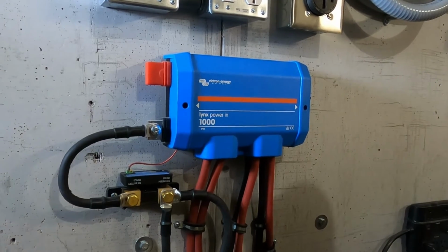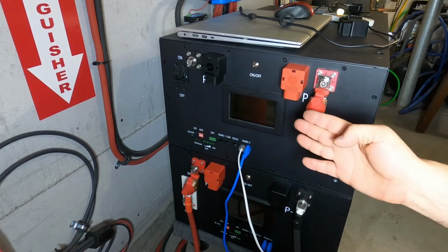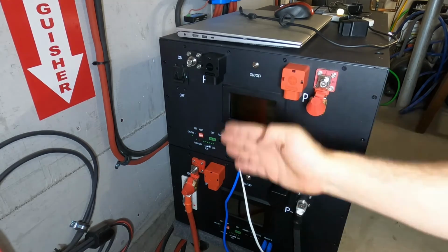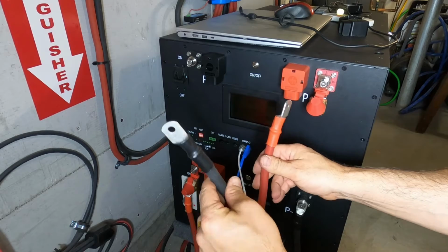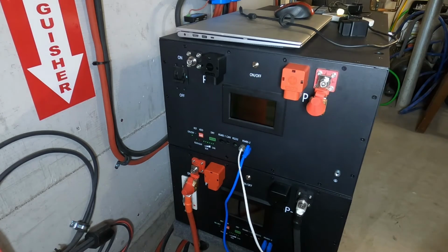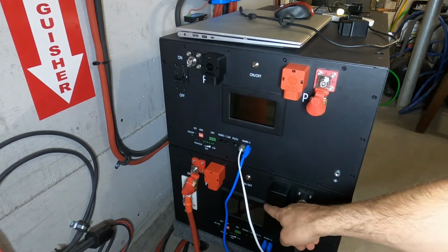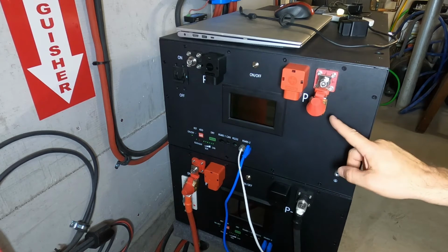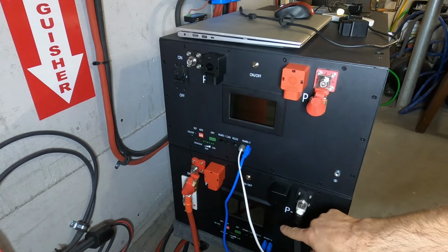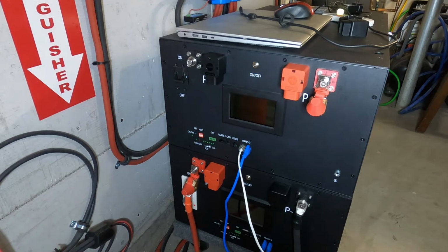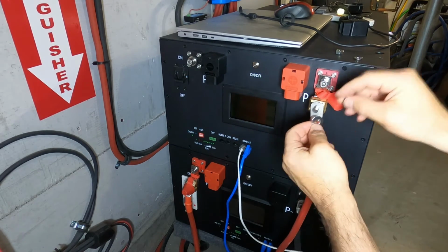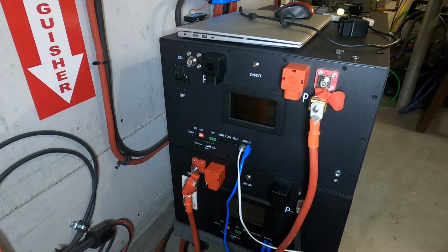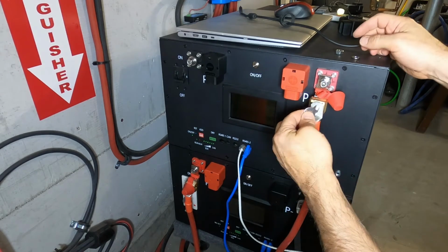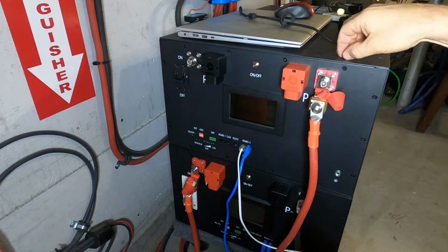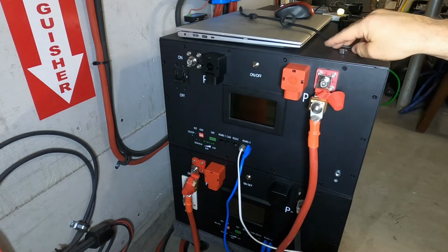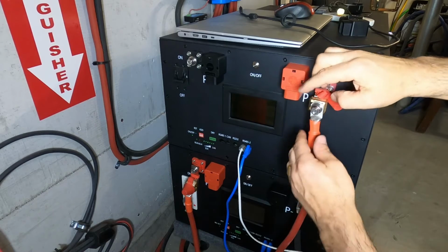All right, ready to hook up the battery. I removed the parallel set of cables I had going between the batteries. Now we have an individual battery set going to each battery, to the bus bar. On the bottom is the Yixiang version 2 battery, and on top is the version 1 battery. I've already secured the cables to the version 2 battery on the bottom. I'm kind of crazy with fuses and breakers - I have a fuse on the terminal for each battery, and a fuse in the bus bar for each battery, so both ends of the cables are protected.